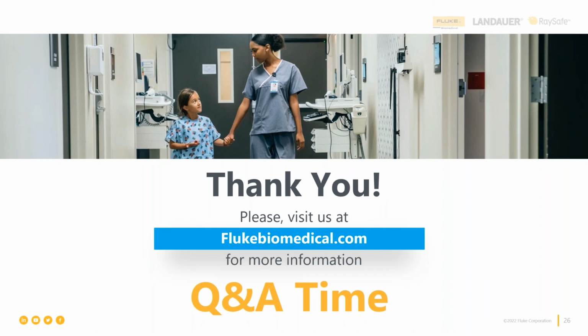Okay. Next question is, how can I use an ESA to test the conductivity of the cleaning solution when testing ultrasound transducers? That's a great question. You cannot use a standard ESA for that. The ULT 800 is specifically designed for that cleaning technician, and it has a conductivity test that needs to be run to make sure that the cleaning solution is sufficiently conductive. Because if they don't mix the cleaning solution dilution properly, they could have a less conductive solution than is required, and that also means that they're not properly mixing that disinfectant solution to do its job as a disinfectant.